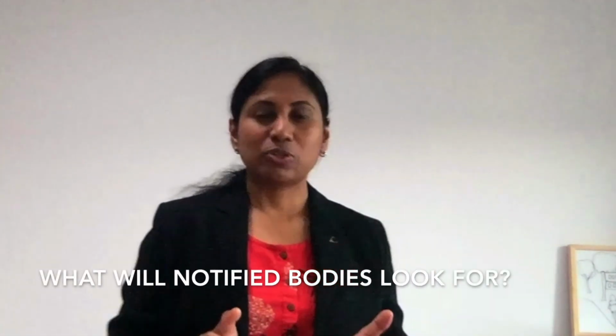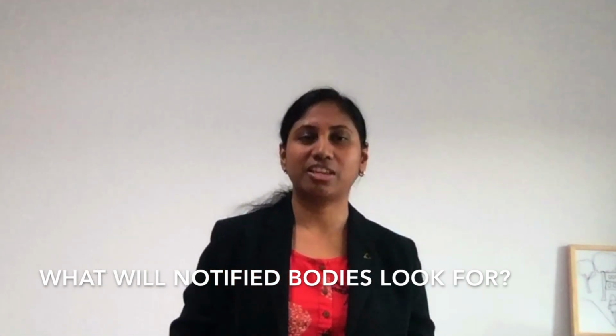So what are the notified bodies going to look for while checking the compliance against Article 15 on the PRRC? Definitely they are going to look at the certificates to confirm the degree of the person according to the MDR. They are going to look at the curriculum vitae. They might look at the job descriptions that the company has issued against the role of the PRRC, the trainings that they have received to perform the tasks as defined in the MDR, the communication within the organization on the appointment of the PRRC, and also the upload of information on the EUDAMED on the PRRC when it becomes available. They could also possibly check the job contracts of the appointed PRRC.